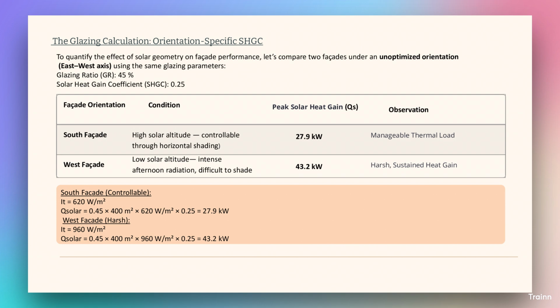South facade, controllable, equals 620 W/m². Qs equals 0.45 times 400 square meters times 620 W/m² times 0.25, which equals 27.9 kW. West facade, harsh, equals 960 W/m². Qs equals 0.45 times 400 square meters times 960 W/m² times 0.25, which equals 43.2 kW.